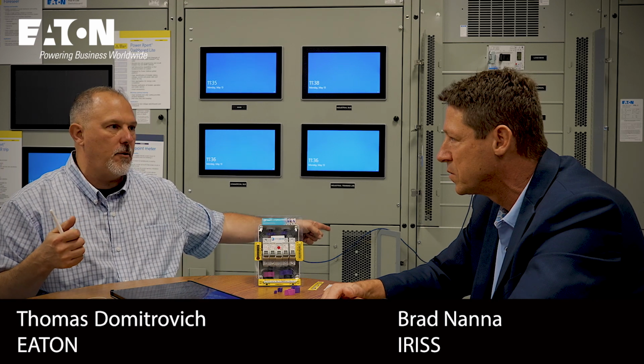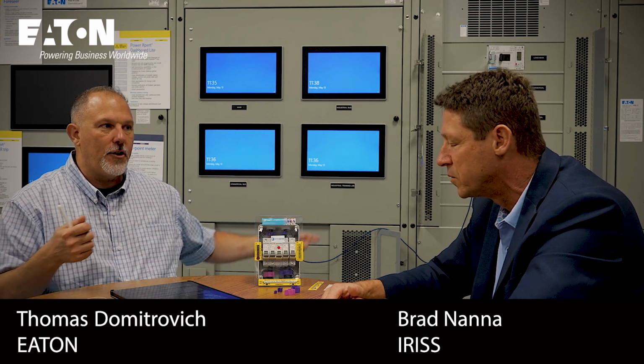So if you're at service entrance equipment, your arc flash boundary, if it's in feet, means anybody within that boundary has to be dressed. I don't know how close you need to be, I'm not a thermography expert. If I'm 20 feet away, can I do thermography on it? I highly doubt it. No, you're going to have to be close.